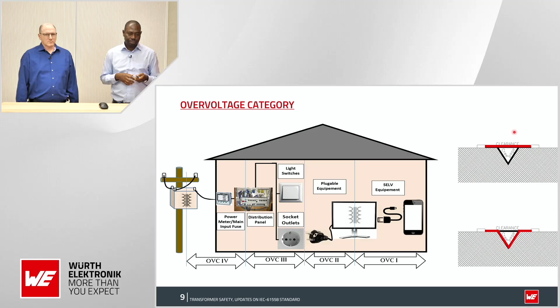Another definition is creepage: the distance along the insulation surface needed to separate the various circuits from each other, to prevent overvoltage breakdown from going from one circuit into the other. That is the concept of creepage and clearance, normally used in the safety world.